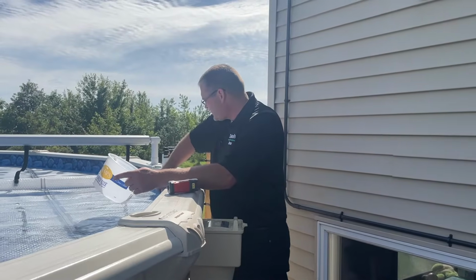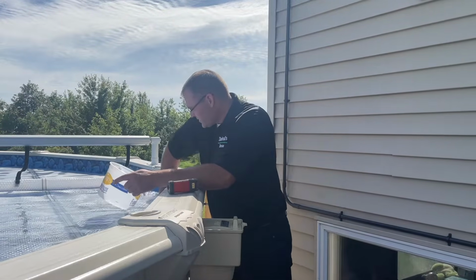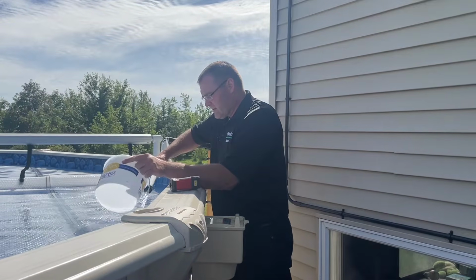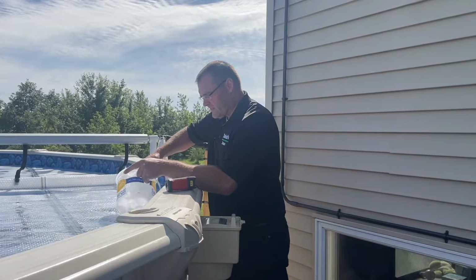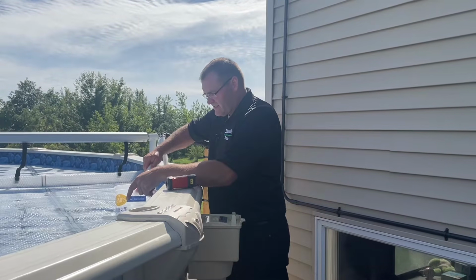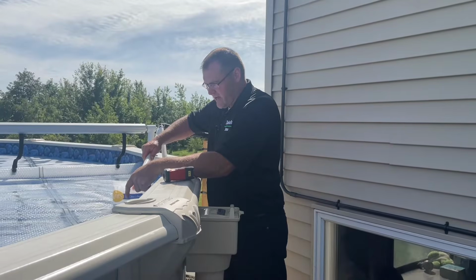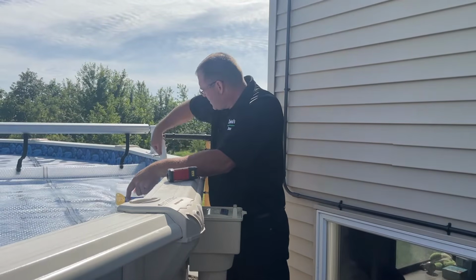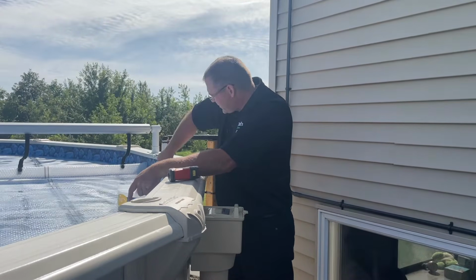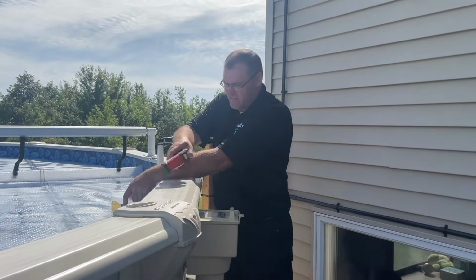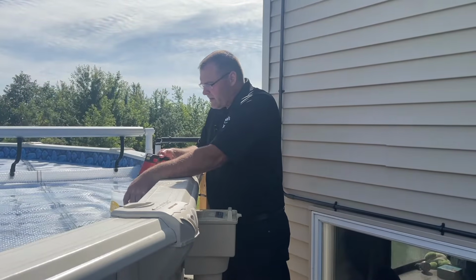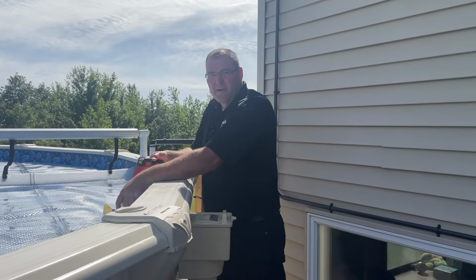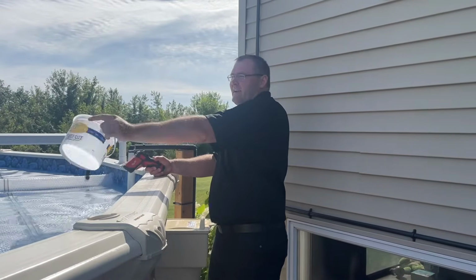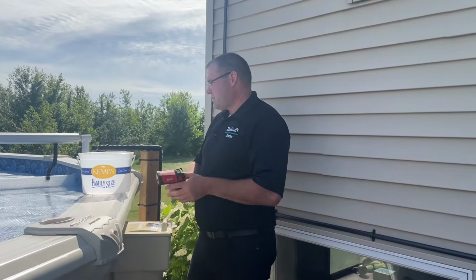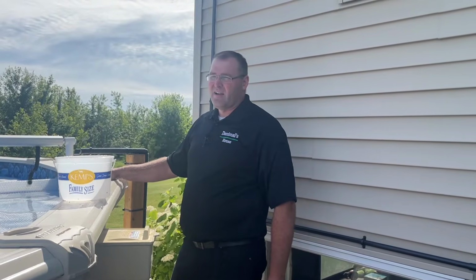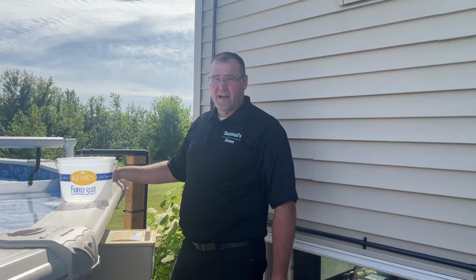With 20 degrees, that's still quite a bit of energy. Let me get this one out of here. This one has way more flow, easily 10 gallons a minute, maybe even more, because I've got that big stainless steel pump going, and this thing's really moving some water. I've got 103 coming out of there. So that's a 30-degree temp rise on 10, 12 gallons a minute.